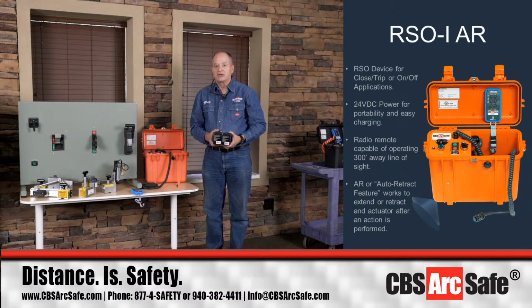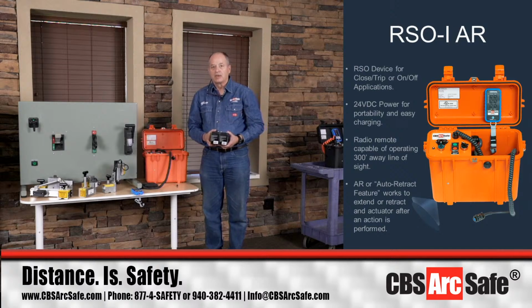Now, you can have batteries that are holding 12 volts, but if they're losing that charge fairly quickly, you need to understand that batteries over time are losing their ampacity, which is the real power of the system. These things have a recommendation to be changed every 2 to 3 years. We've seen them last longer, and we've seen customers kill them inside of 6 months from deep cycle drains.